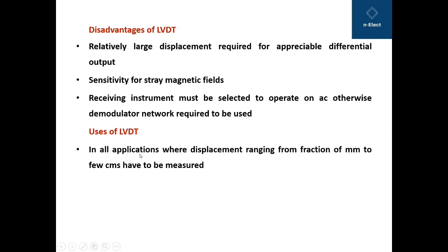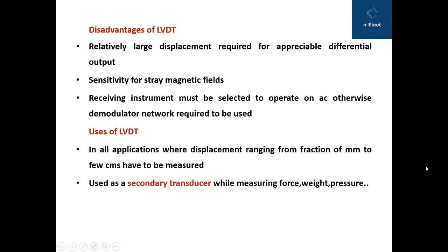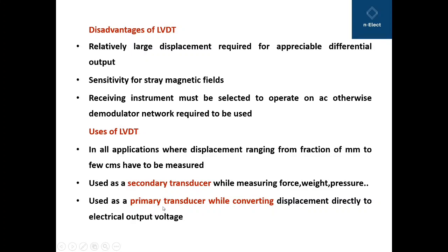LVDT can be used in all applications where displacement ranging from a fraction of a millimeter to a few centimeters must be measured. It is used as a secondary transducer while measuring physical quantities like force, weight, and pressure — for example, in a Bourdon tube and LVDT combination for pressure measurement. It is also used as a primary transducer when converting displacement directly to an electrical output voltage. This concludes the discussion on inductive transducers through the example of LVDT, covering its graphical characteristics, advantages, disadvantages, and uses.